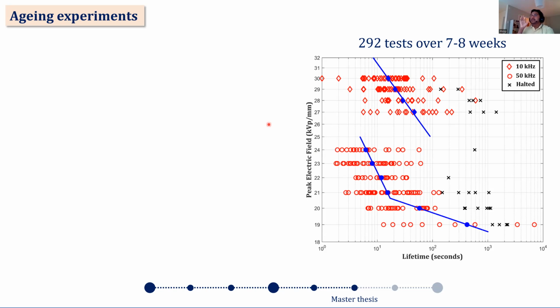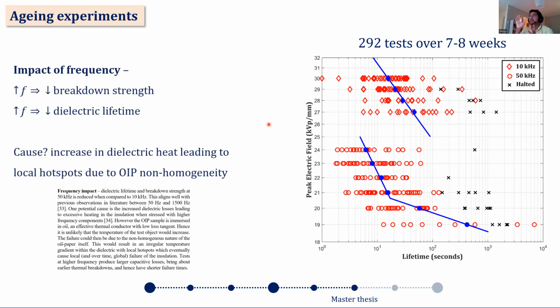Now, there were two major types of observations from this graph, and I want to go through them one by one. The first observation was the impact of frequency. It is very clear that an increase in frequency causes reduced breakdown strength, shown by the downward shift of the 50 kilohertz line with respect to the 10 kilohertz. The second is that an increase in frequency also reduces lifetime, denoted by the leftward shift in the 50 kilohertz line. The cause of this, according to literature, is increased dielectric losses.